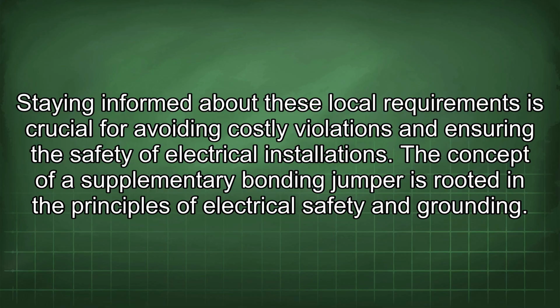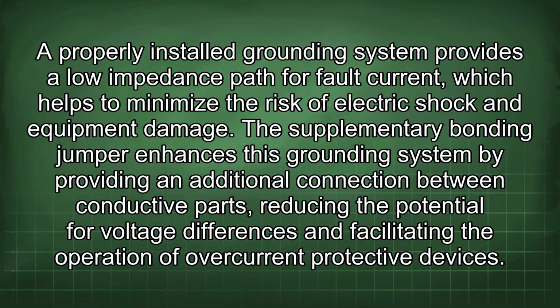The concept of a supplementary bonding jumper is rooted in the principles of electrical safety and grounding. A properly installed grounding system provides a low impedance path for fault current, which helps to minimize the risk of electric shock and equipment damage. The supplementary bonding jumper enhances this grounding system by providing an additional connection between conductive parts, reducing the potential for voltage differences and facilitating the operation of overcurrent protective devices.